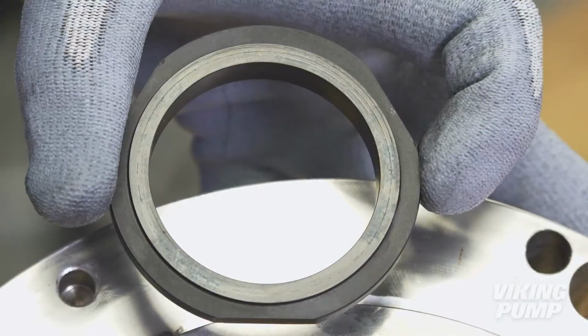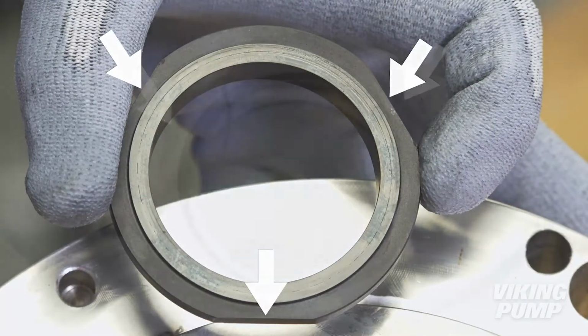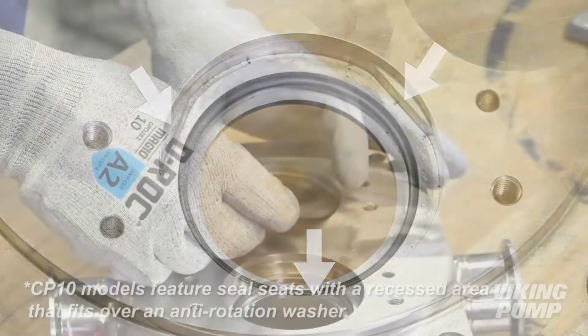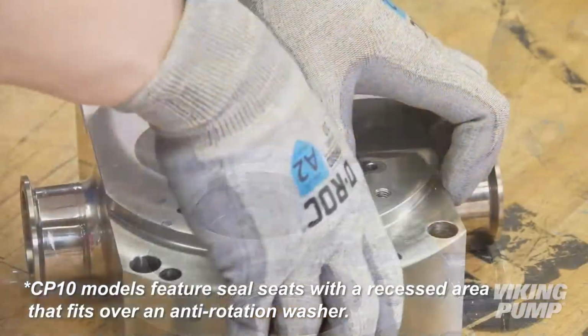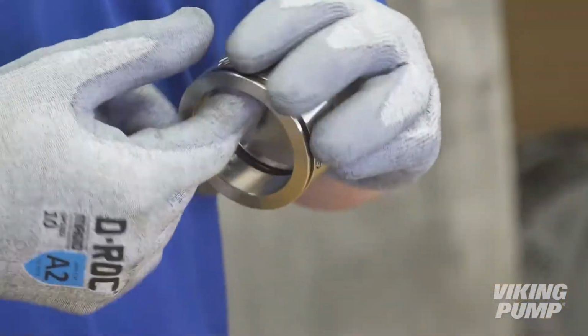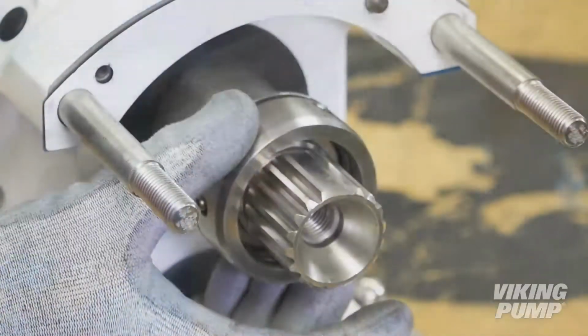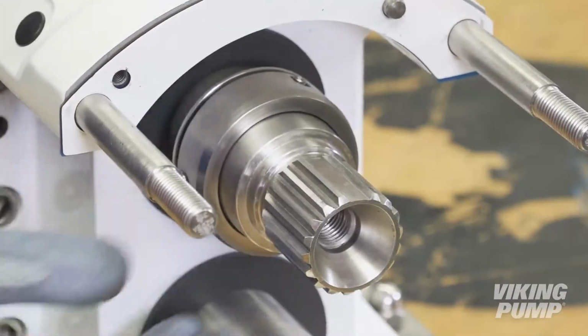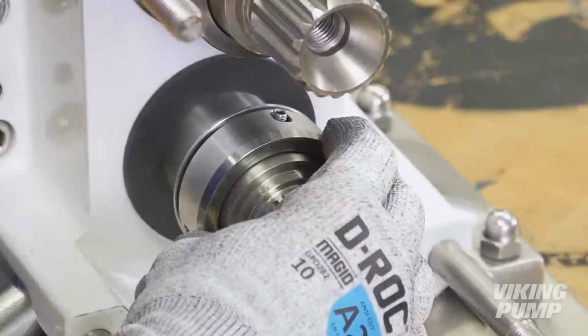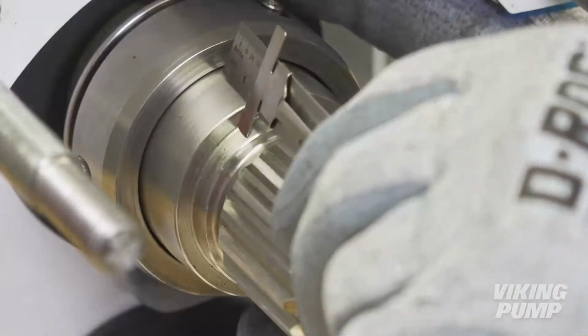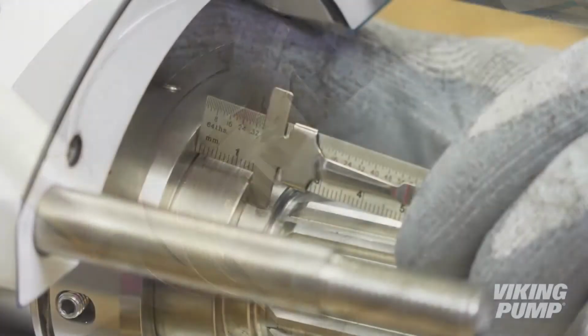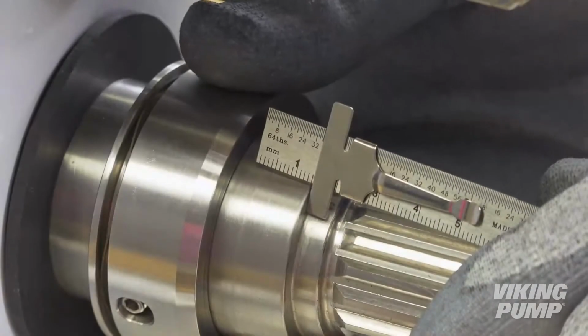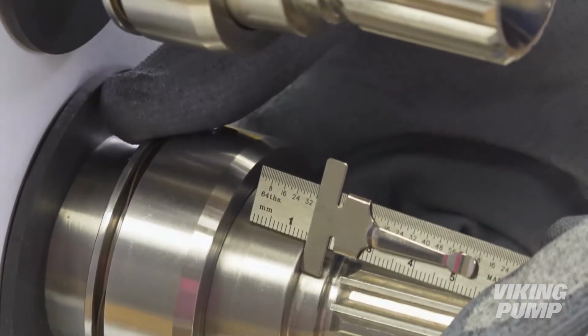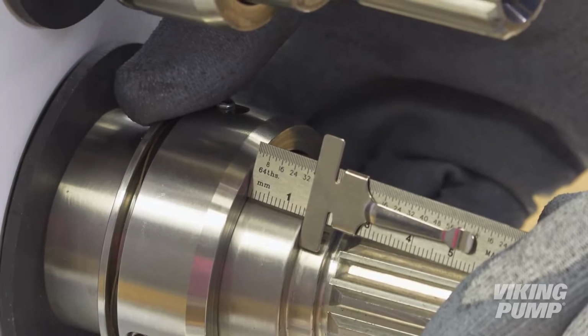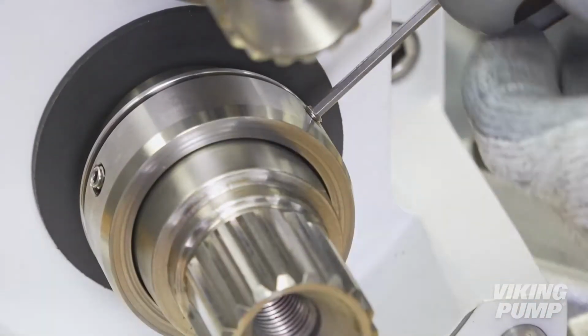Next, install the stationary seal seats. The triangular shape of the seal seat must locate fully in the rotor case bore. Lubricate and install the new rotary seal cartridges and O-rings onto each shaft. Using a ruler, set the seal to its correct position on the shaft. This measurement can be found in the technical service manual. Failure to set this distance correctly could result in rapid wear or immediate seal leakage.